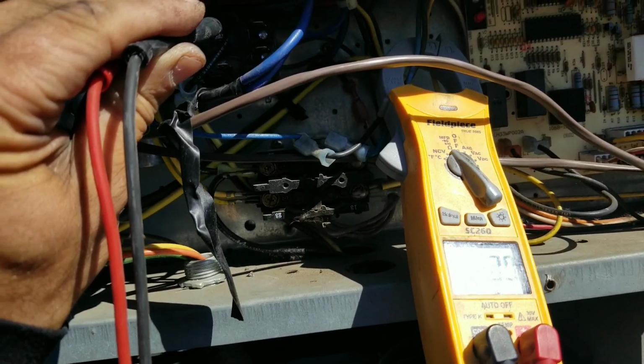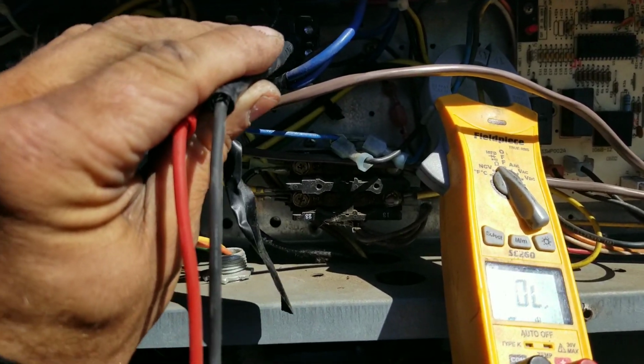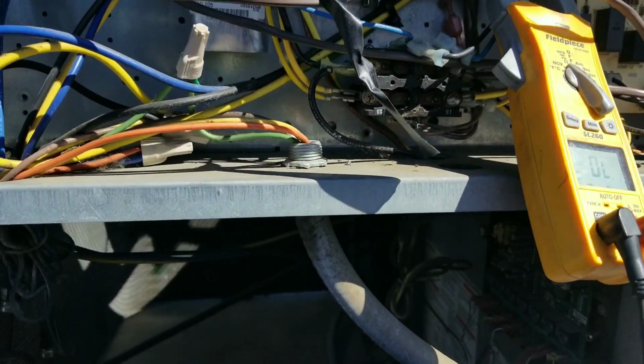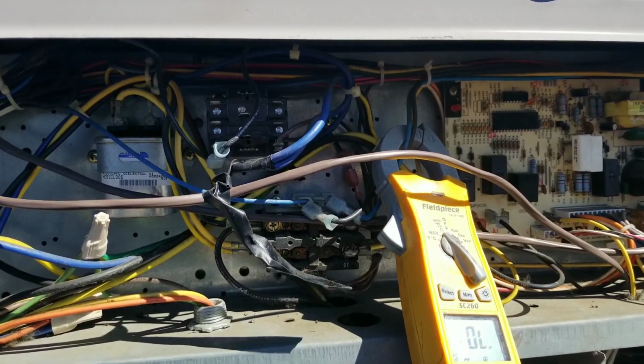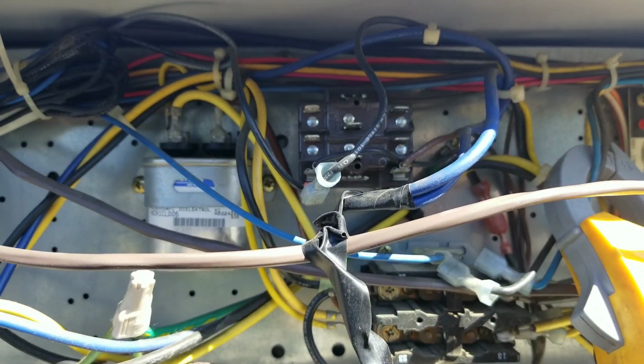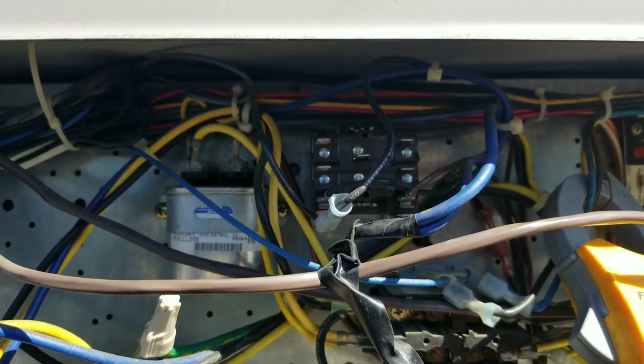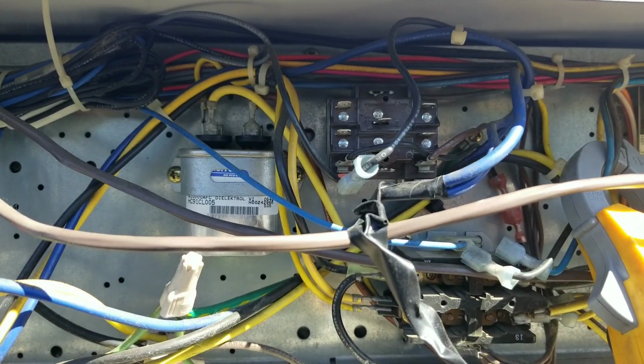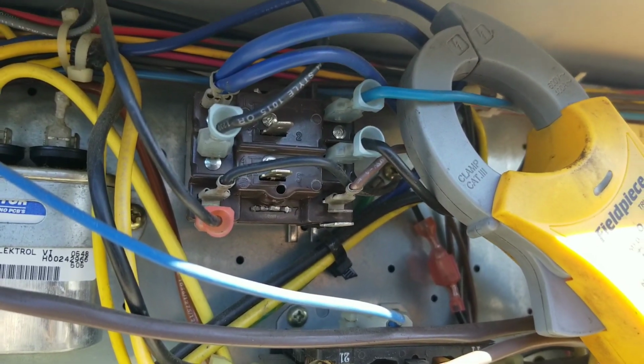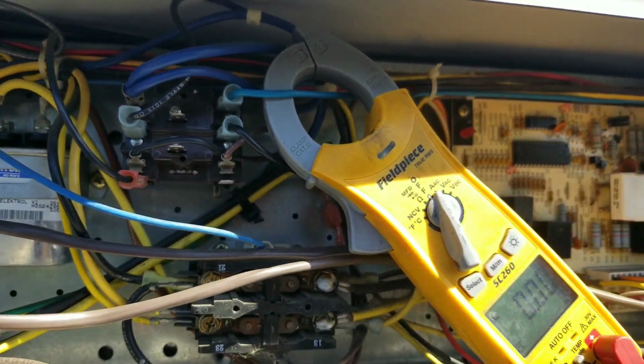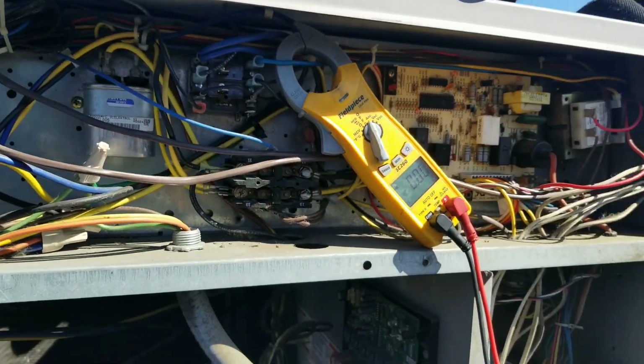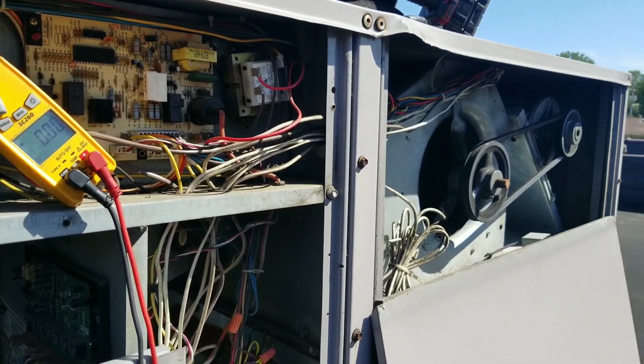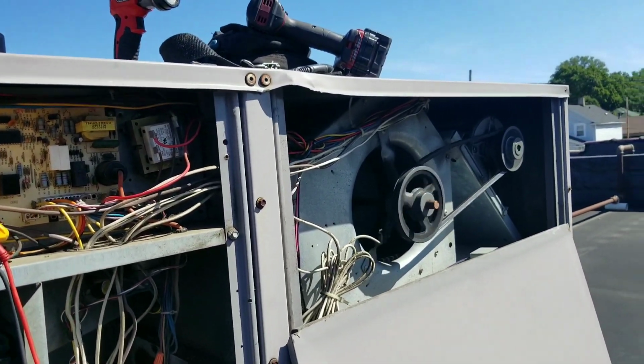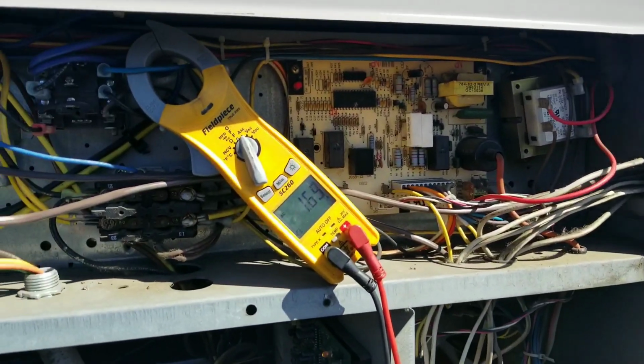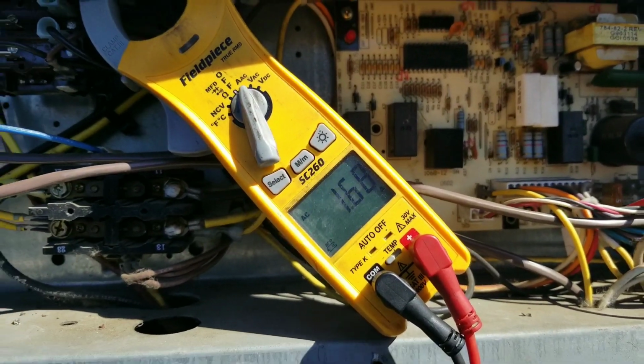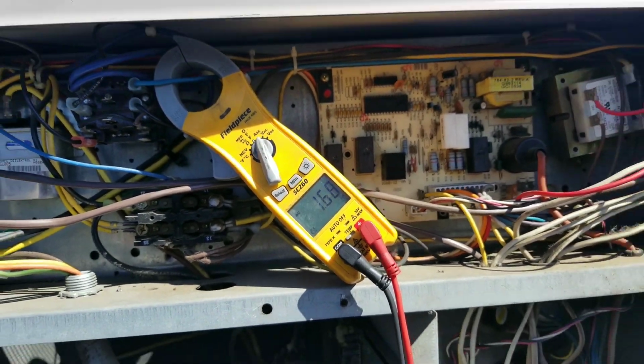You'll notice we have continuity across our relay now. All right. Let me get this motor wired back up and we'll power it back on, see if that blower turns on now. My relay's all wired up. My amp clamp is set up. Let's power it on and see if that blower comes on. There's our blower. Pulling 1.6 amps.